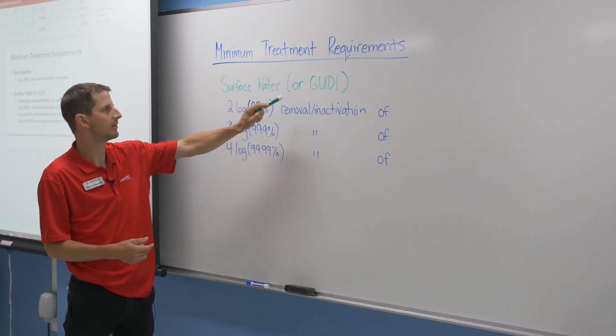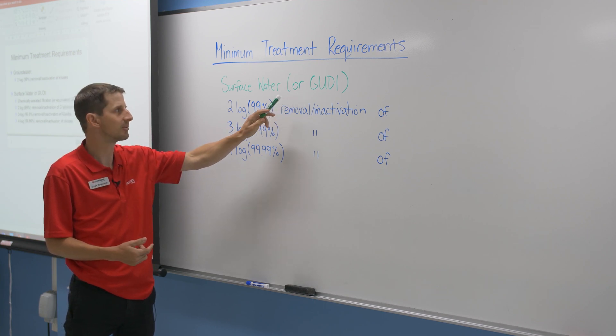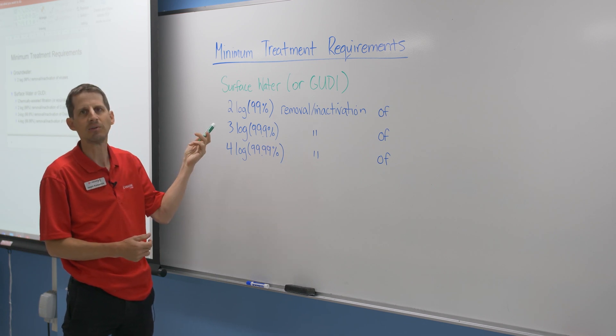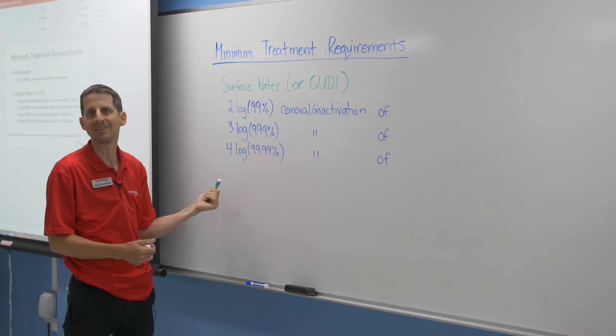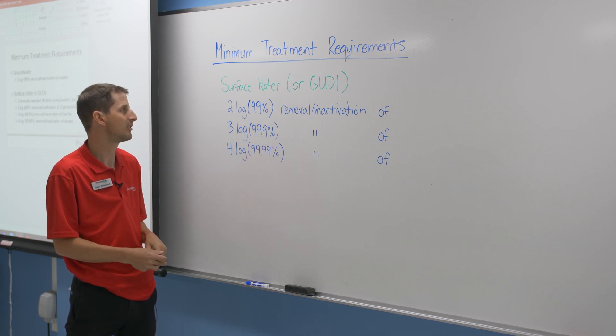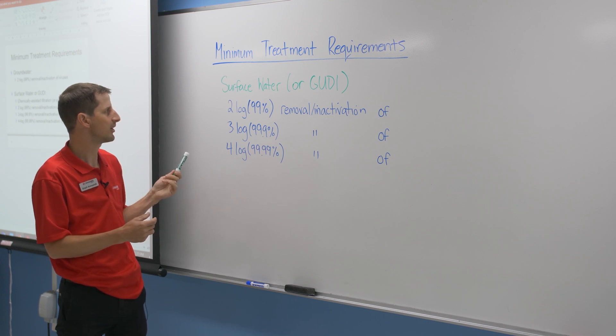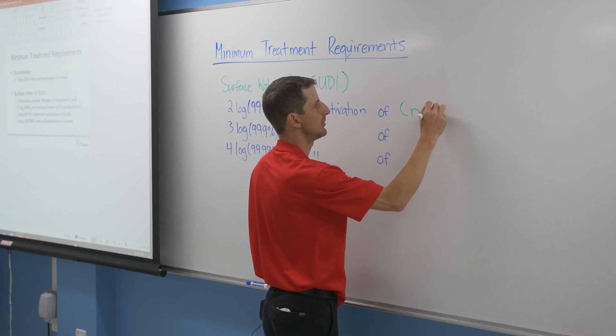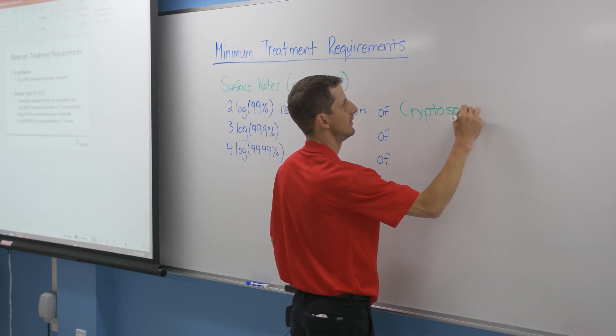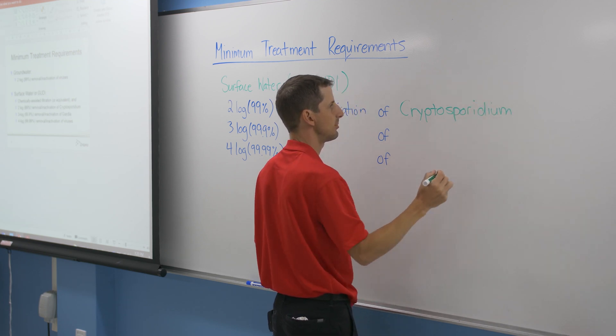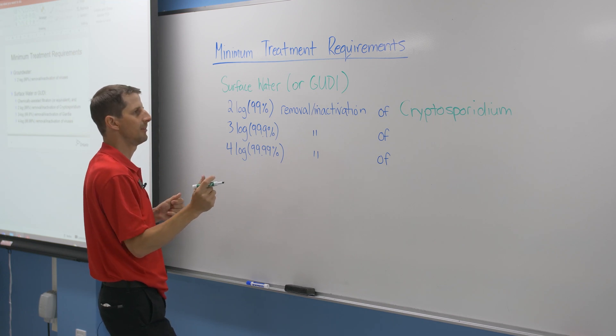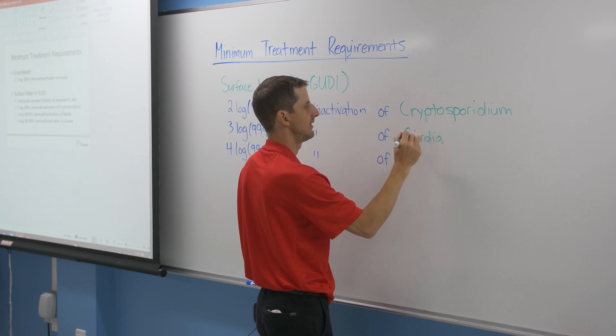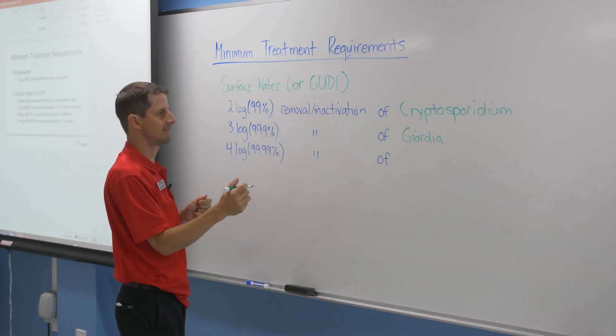For surface water, or GWUDI — groundwater under direct influence of surface water — we have to follow these treatment requirements. We need chemically assisted filtration, and this table says we need chemically assisted filtration plus removal of three bugs. The three bugs we need to remove are cryptosporidium — some people call it crypto — which is that big protozoa that really showed up in the 1990s with a lot of outbreaks. The second is Giardia lamblia, otherwise known as beaver fever, another protozoan. And the last one is viruses.